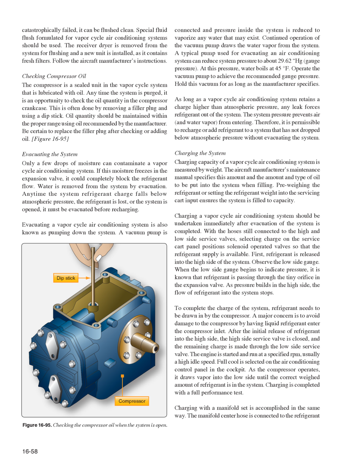Only a few drops of moisture can contaminate a vapor cycle air conditioning system. If this moisture freezes in the expansion valve, it could completely block the refrigerant flow. Water is removed from the system by evacuation. Anytime the system refrigerant charge falls below atmospheric pressure, the refrigerant is lost, or the system is opened, it must be evacuated before recharging. A vacuum pump is connected and pressure inside the system is reduced to vaporize any water that may exist. Continued operation of the vacuum pump draws the water vapor from the system.